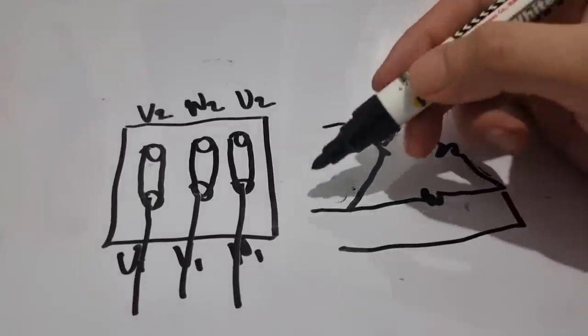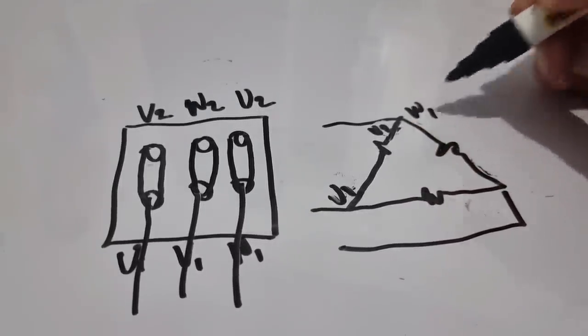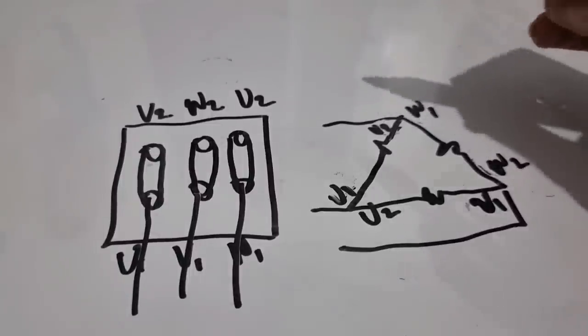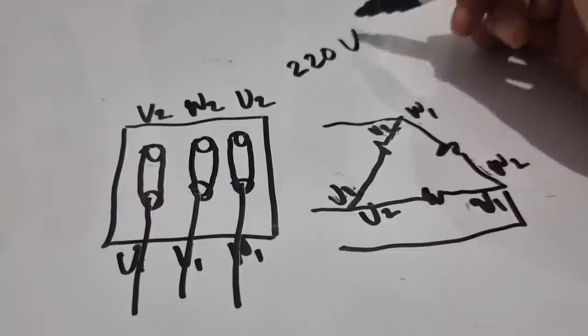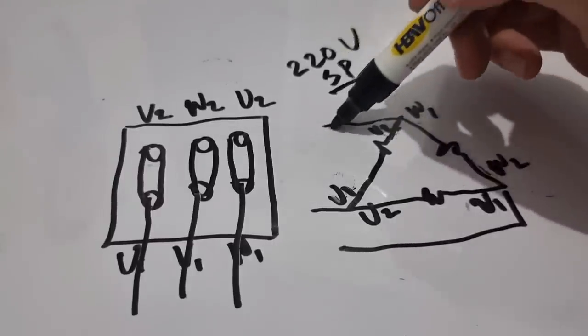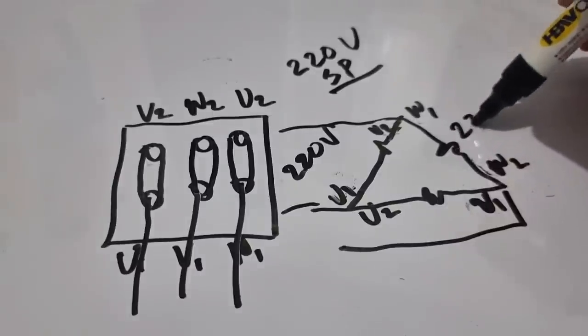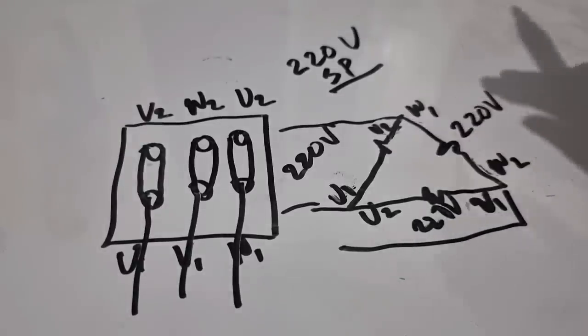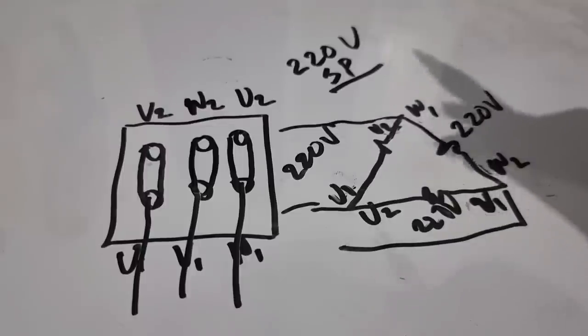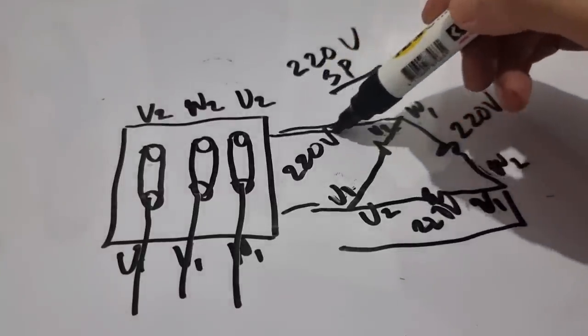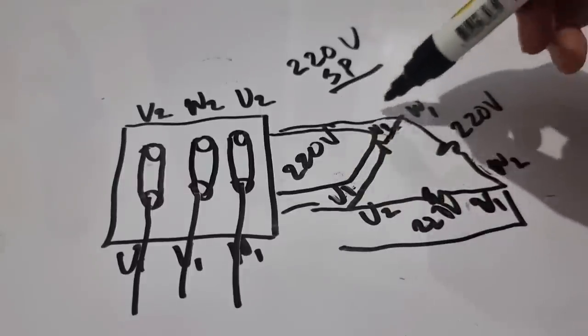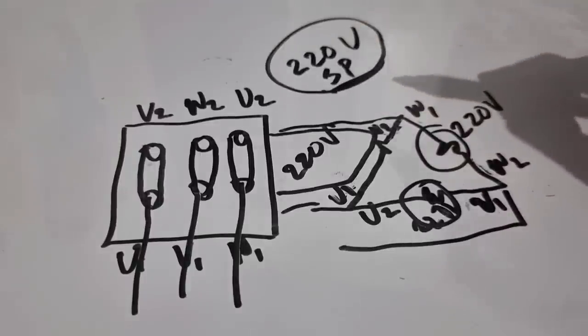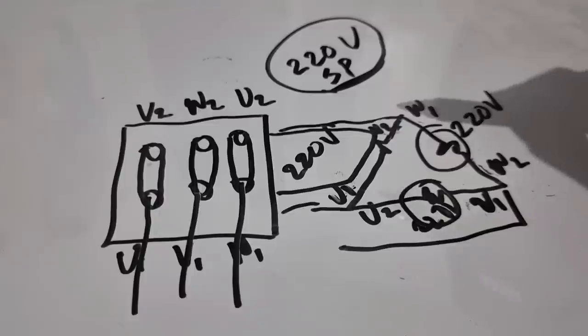So this will be your U1, U2, then W1, W2, and then V1 and V2. This is the delta connection. As you can see, if you have 220 volts three-phase, then this winding is 220 volts, this winding is 220 volts, and this winding is 220 volts — going directly to each winding of the motor. If 220 volts passes onto each winding, you have three-phase 220, and this is the current setup on this motor.